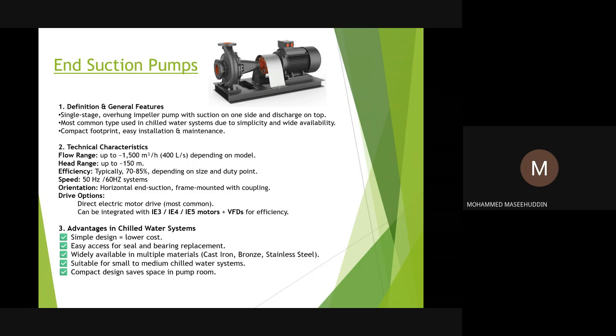Why small to medium? Because these are capable of handling a certain pressure, up to 16 bar only. So it can cater to the small range up to the medium range. You cannot go with a higher range of capacities, because the nominal pressure and the casing pressure of these pumps are limited to a maximum of 16 bar only. And the compact design, of course, saves space in the pump room as well.